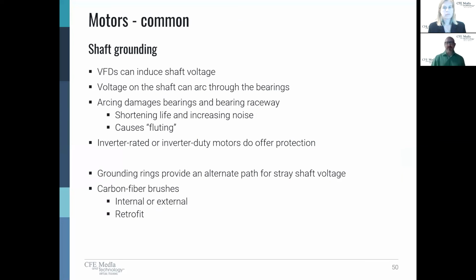And you can do inverter rated motors and inverter duty motors. And they basically have beefed up windings to handle those voltage spikes so they don't break down prematurely. But just because you have an inverter rated motor doesn't necessarily mean that you have grounding. So I say they do offer protection. I should actually say they do not offer protection. So that is something that you're going to want to coordinate with your motor specifier.